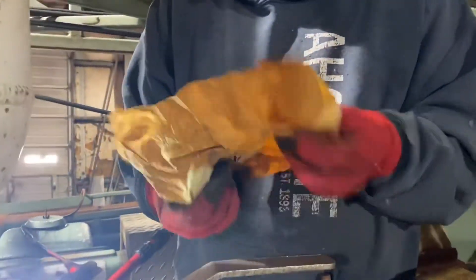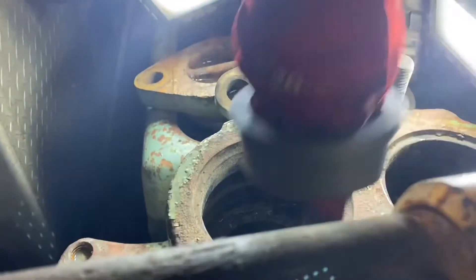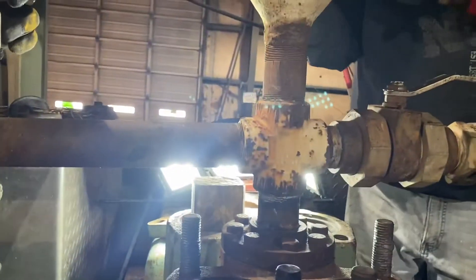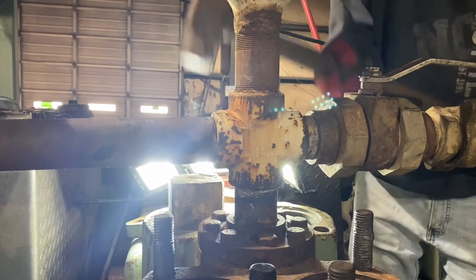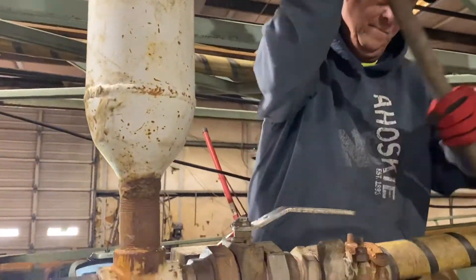Lynn's opening a brand new valve seat and he's going to drop it in there. Brand new — look at that. No grease — you definitely don't want grease. And that's the custom 4x4 we made; we shaved the corners off of it so it would fit. That way it fits nice. And then we get our big hammer and we tap it four or five times. Make sure it seats. And we're done.